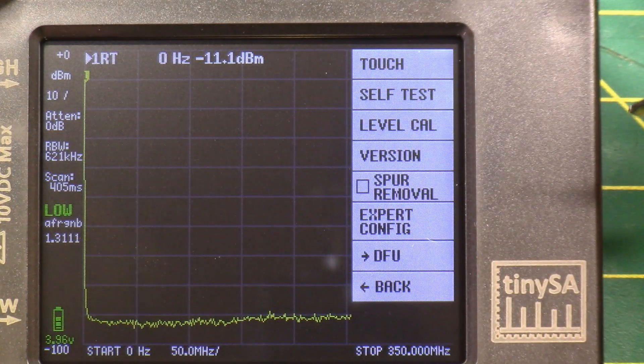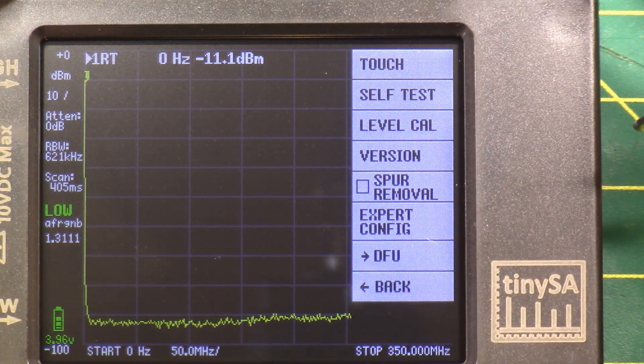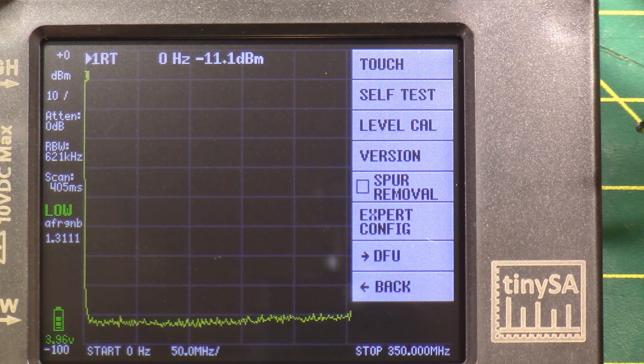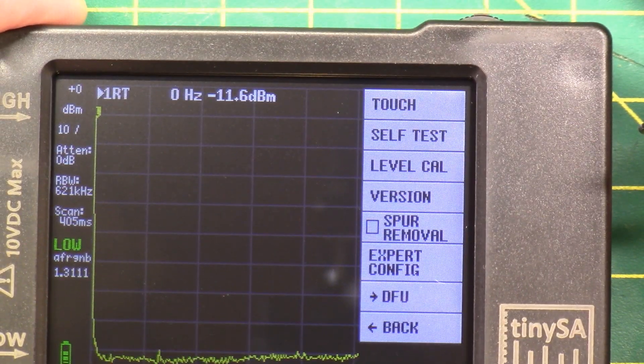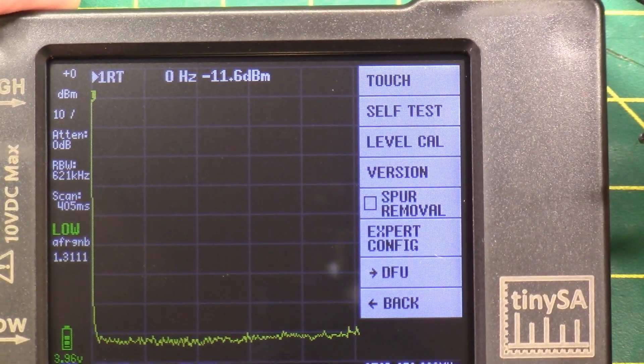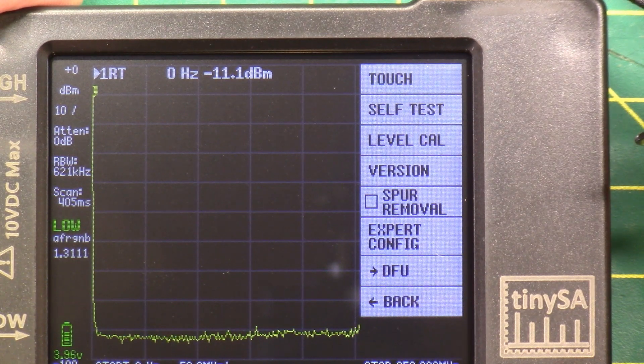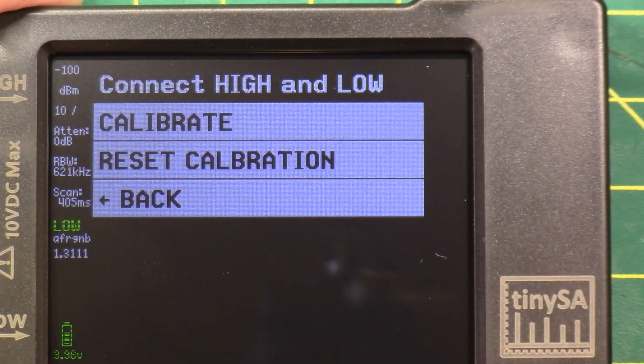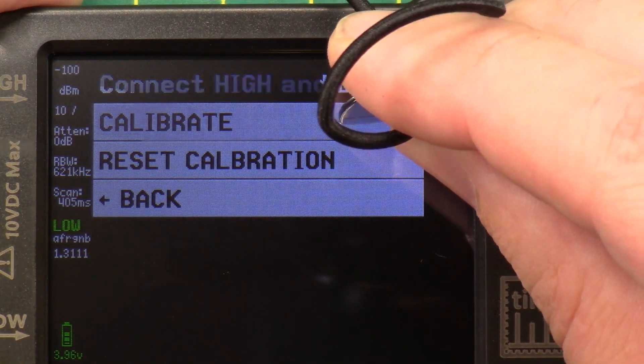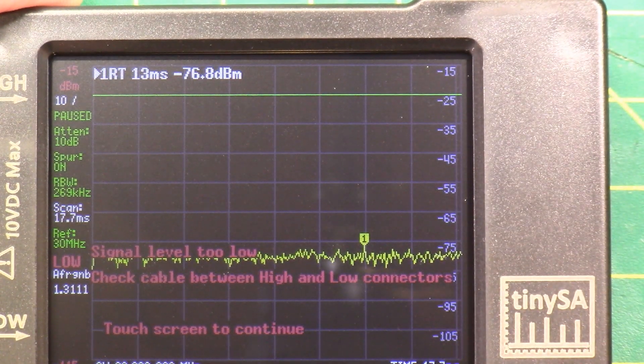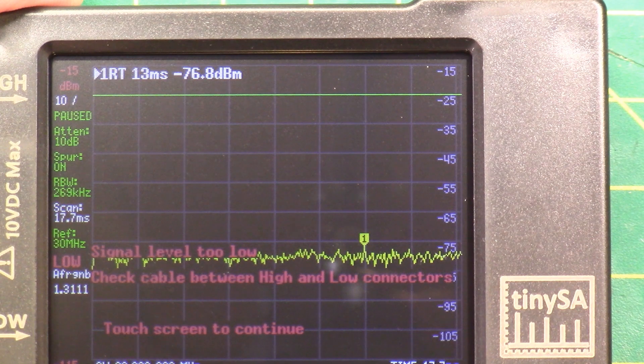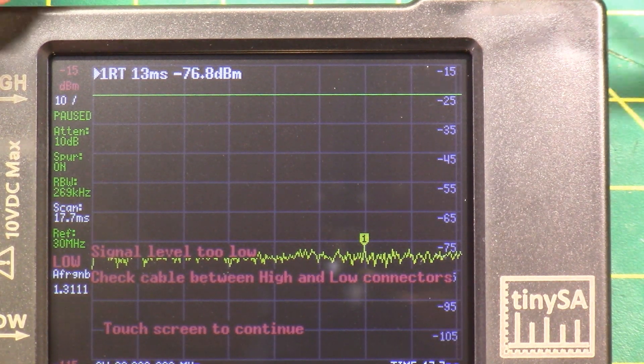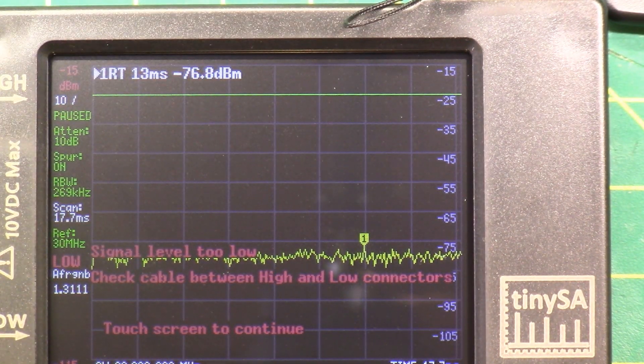Let's do config, touch, self-test, level calibration, version, spur removal. Let's hit level calibrate, and let's hit calibrate. Signal level too low, check cable between high and low connectors, which is what I expected to see. What they want you to do is they want you to take this little SMA gender changer and these two SMA test leads, and they want you to connect them together.